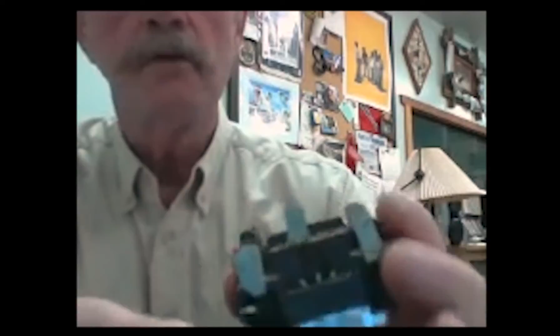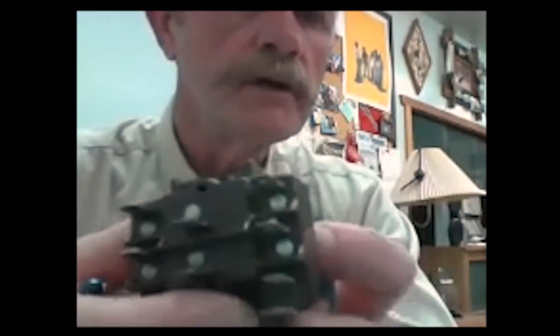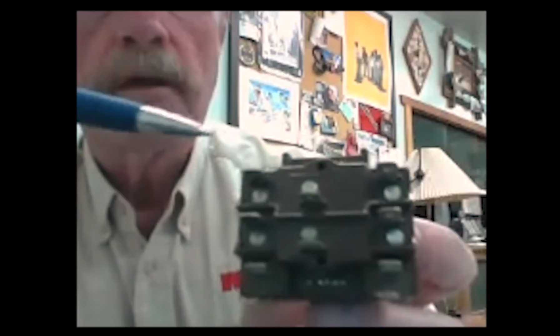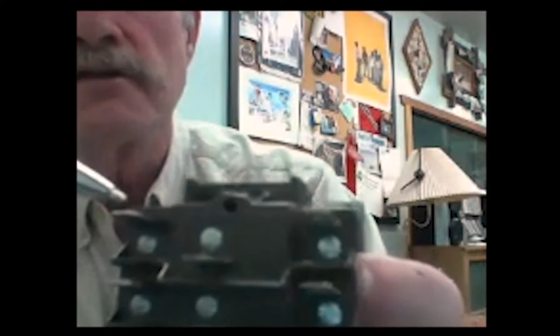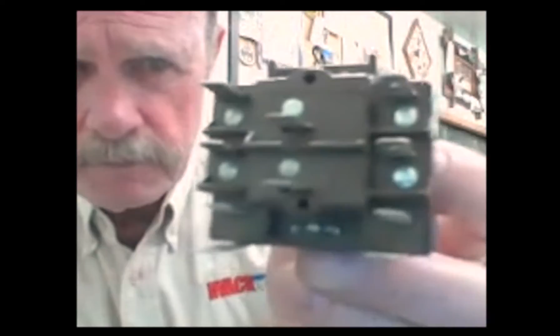Now the points themselves - I'm not sure if we got good enough video here to see them, but I'll try. On the face of the relay, you have this point, and there's a line embossed in the plastic showing a normally closed switch between this point and that point. It also shows a line going from this point over to this point, showing an open switch symbol. I don't know if you can see that. One symbol shows normally closed, and the other shows normally open.